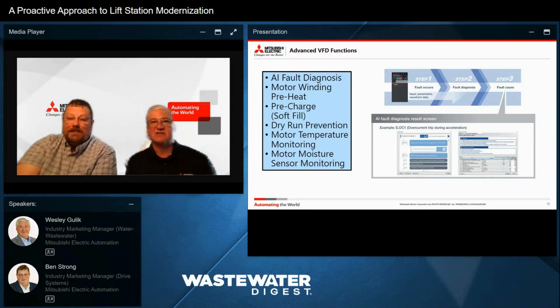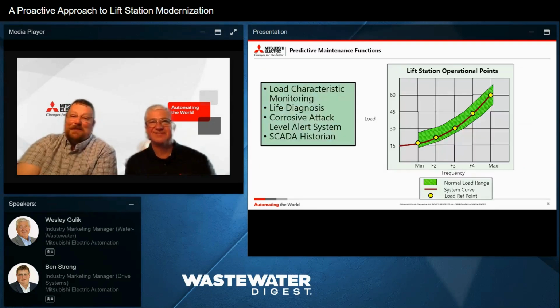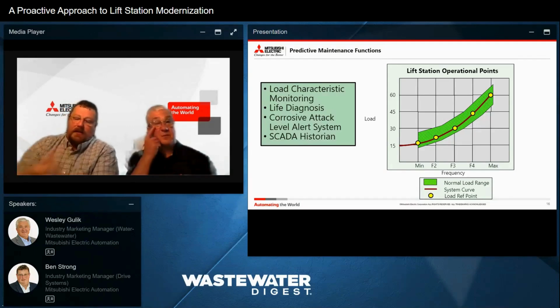Risk tolerance. What's your risk tolerance? Everybody's different. So, load characteristic monitoring: most VFD manufacturers have something like this. Earlier, I was talking about AI, or where the VFD can learn your application. It's typically 5 operating points that you can either set or the drive can measure about your operation, and then defines a normal operating range.